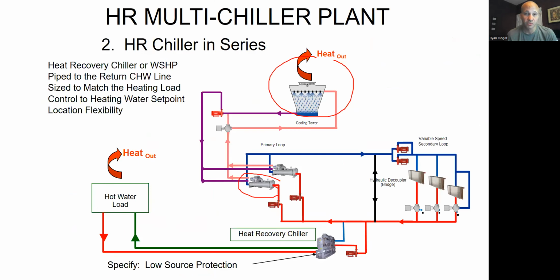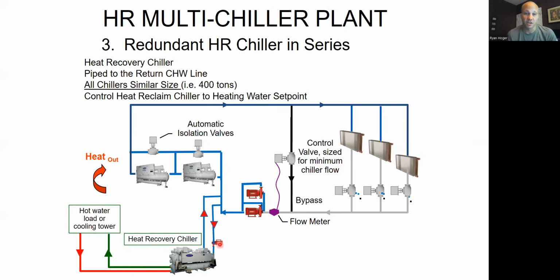All right, so differences on this one versus that one. This guy's piped into the chilled water line just like the other guy was. I'm controlling it based on the hot water set point, right? But over here, I was sizing the chiller for the heating load. And in this case, I'm sizing all these chillers relatively equal to each other, so I can kind of control them in a similar fashion. It's not a ton different than the last one, but it's a little bit different in the concept of it because I can flow the water a little differently. These are different ways that you could pipe these guys in.